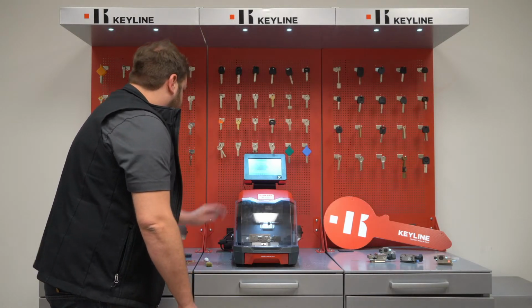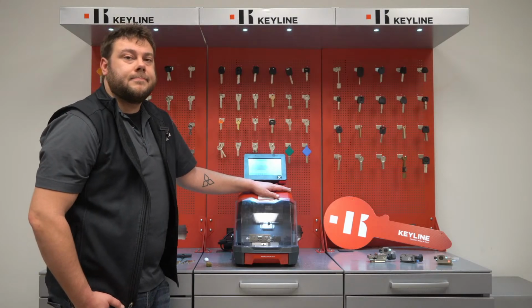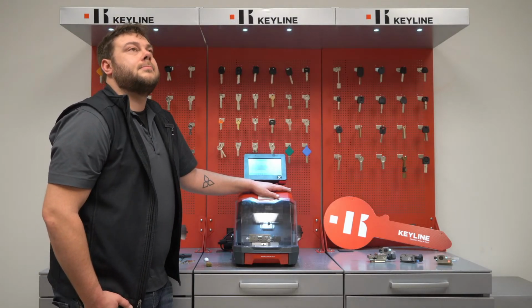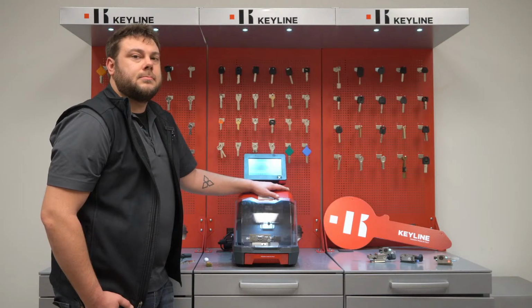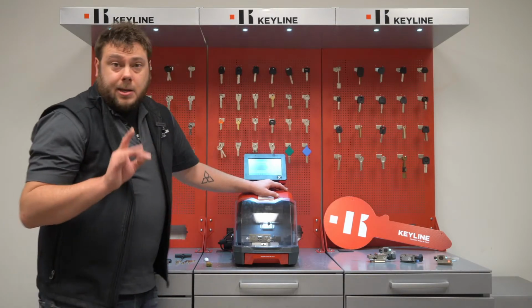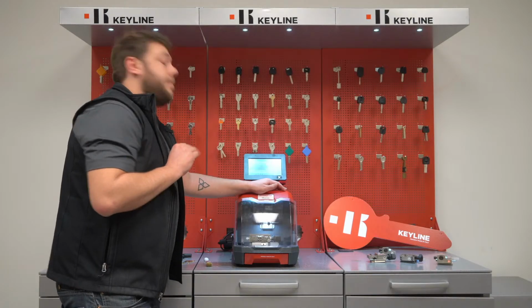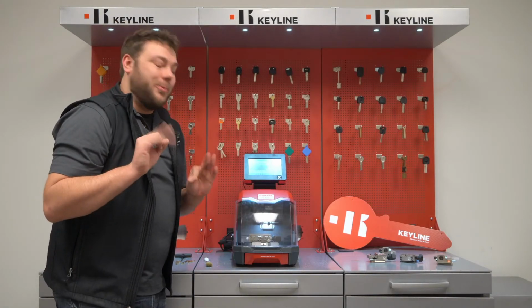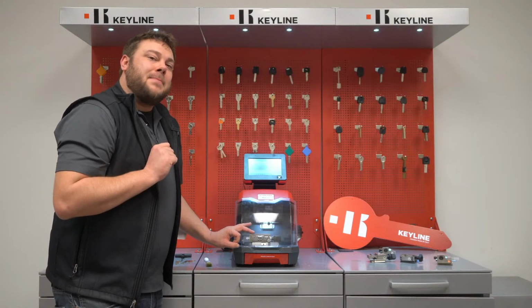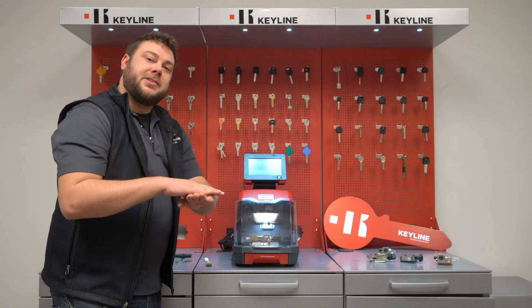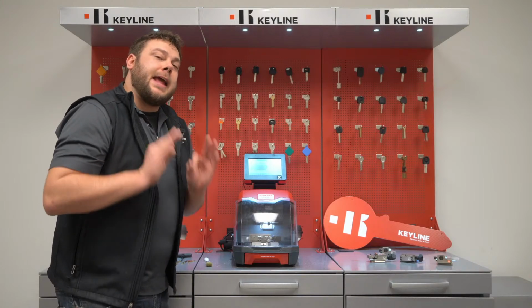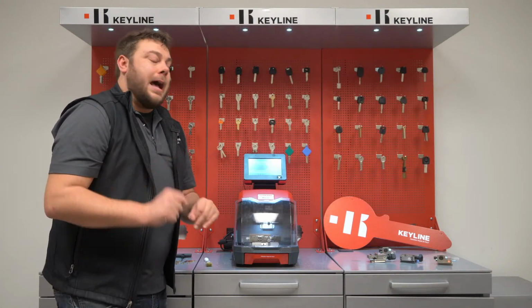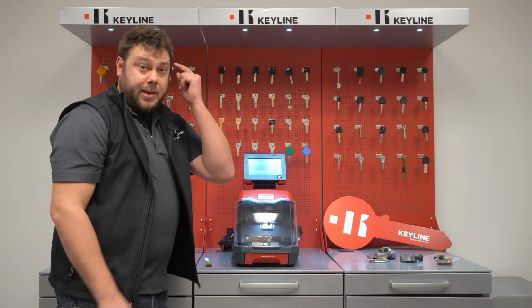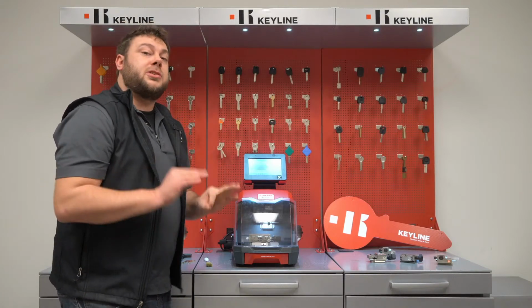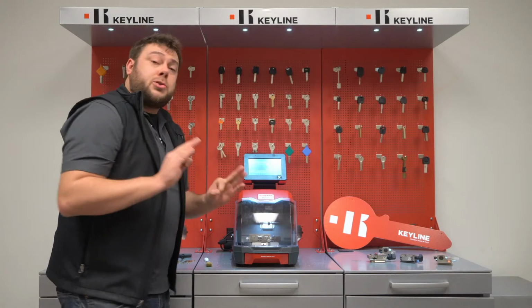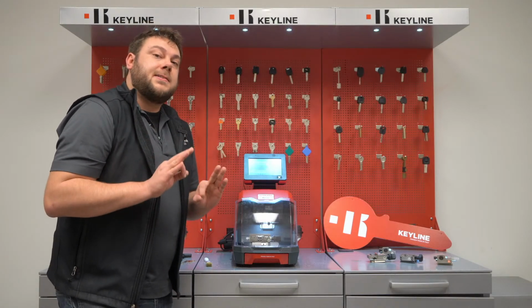All right. Can you maybe review some of the common error codes people may get and how they push through those? Cool. All right, so common error codes that you get. The main one, invalid jaw, when you have the proper jaw installed. That means that the tracer's either touching or not touching the jaw where it's supposed to. Doing a calibration should fix your issue. I like to do a full calibration because that way I know 100% in my head that the machine is calibrated. You can usually sometimes get away with just doing a jaw setup.